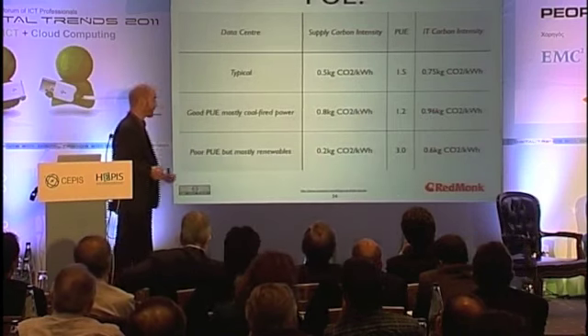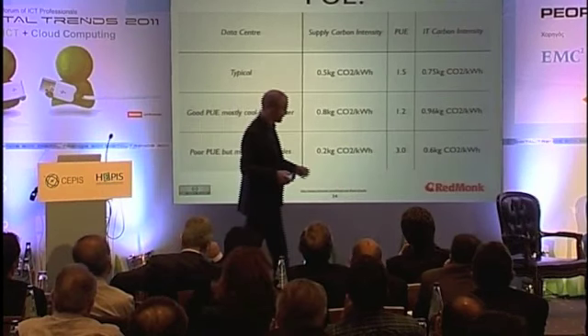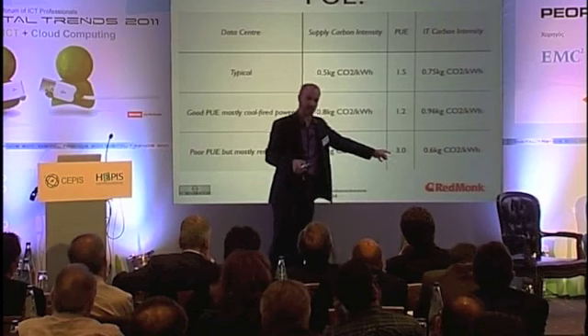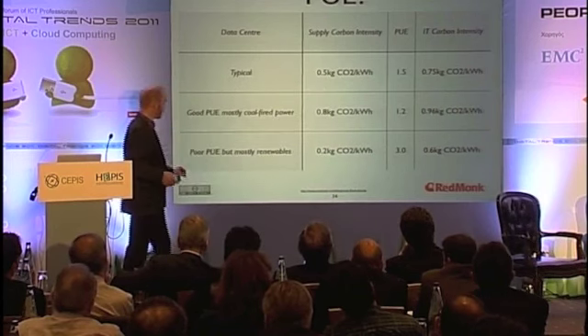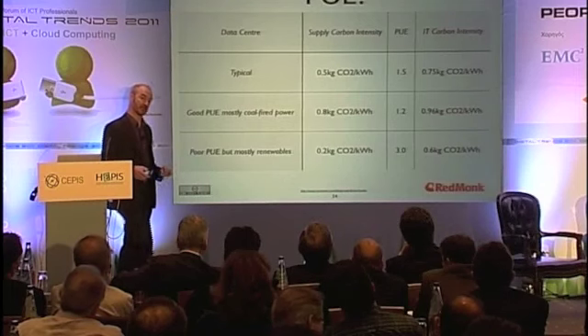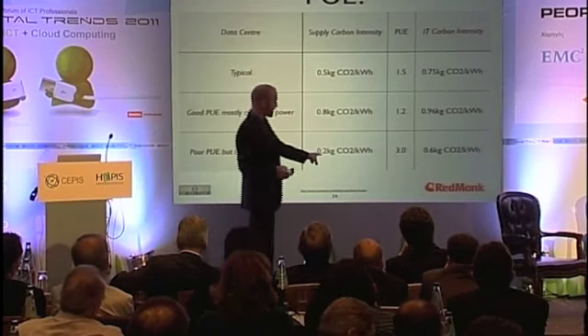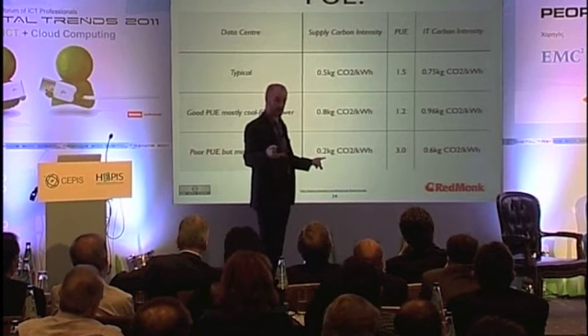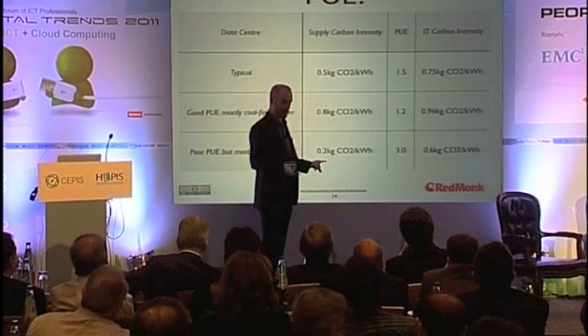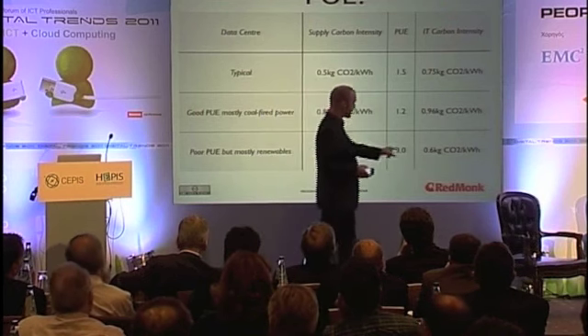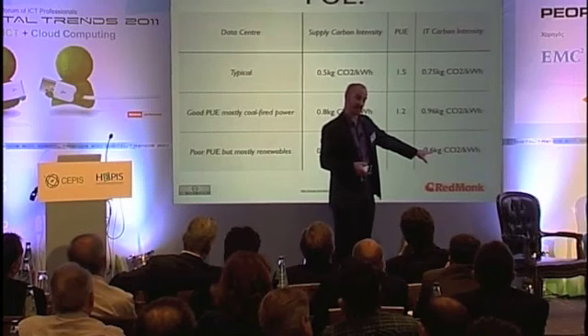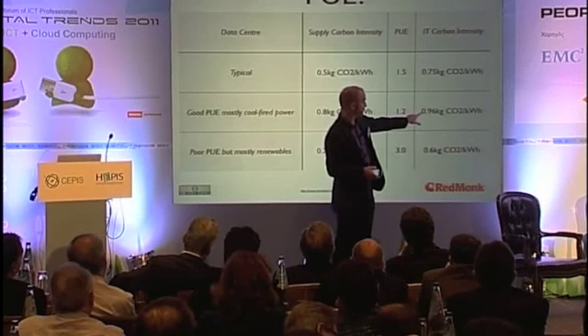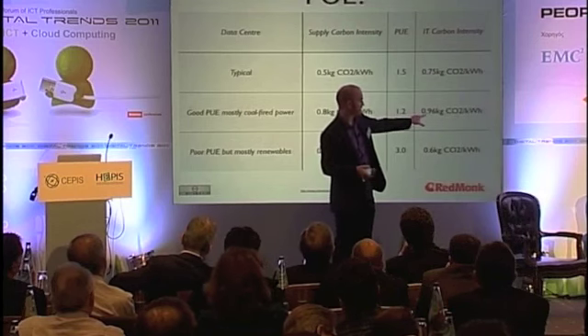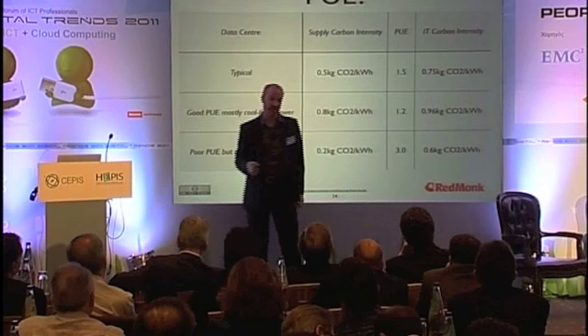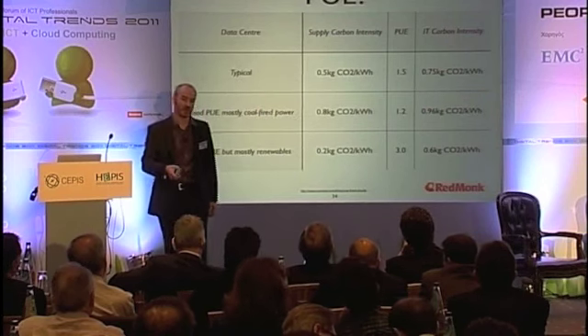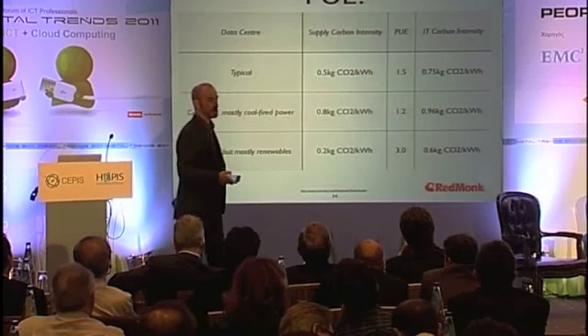On the other hand, if you've got a really bad data center with a PUE of 3, very inefficient, but it's powered mostly by renewables, your carbon intensity on supply might be 0.2, which is still significant, there's still carbon being produced per kilowatt hour. 0.2 times 3 gives you 0.6, which is significantly less, it's 60% of the carbon intensity of the data center with a PUE of 1.2. So PUE is no indicator whatsoever of how green something is.